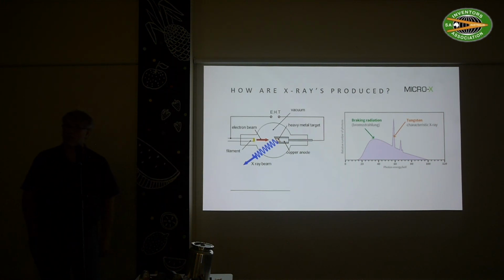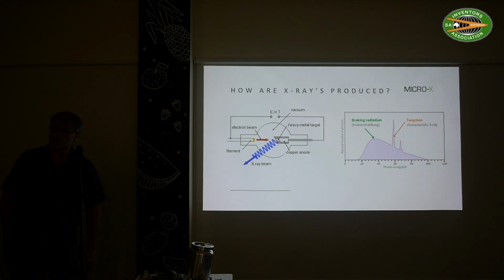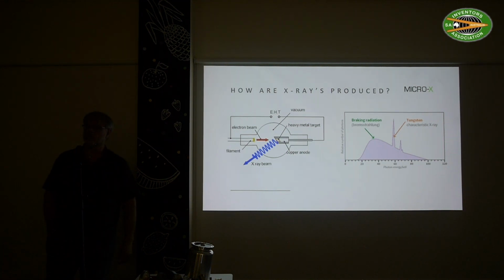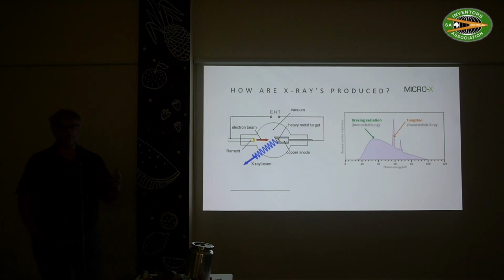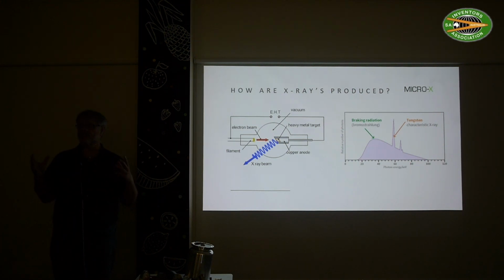Yes? Is that dangerous to biological tissue if someone was to stand in front of that? Sorry, I didn't get that. Would that be dangerous to biological tissue if someone was to stand in front of an X-ray of such high energy? Would that be too dangerous? Absolutely. With X-ray, the golden rules when you talk about safety are distance, duration and intensity. So all those factors come into account. And in very technical terms, we talk about a thing called mAs, M-capital-A-S, which stands for the milliamps of current that goes through the X-ray tubes, times the time in seconds, and that gives a particular value.